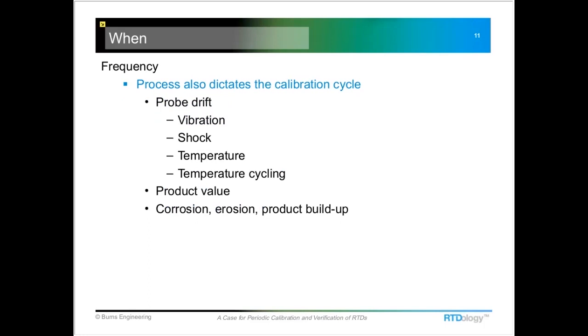Sometimes the process can help dictate what the calibration cycle is. I mentioned vibration. There's also shock, there's temperature cycling, and then the actual temperature that the process is running at. Higher temperatures will cause the temperature probes to drift a little bit more. I mentioned water hammer can do it, and then temperature cycling. The product value, again, typically in a batch process, you'd want to do it before and after. And finally, if you have a corrosive product, that can start eating away at the thermal well, or if it's a direct immersion probe, it can start eating away at the probe itself. Erosion will do the same thing. When either of those starts to happen, the time response of the probe can slow down a little bit, which may result in an inaccurate temperature reading.